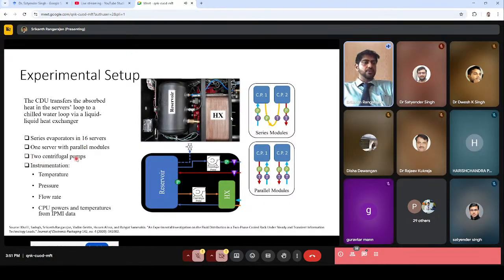And we had 2 centrifugal pumps. We did some instrumentation for noting the temperature, pressure, the flow rate, and CPU powers and temperature from IPMI data. You can see that there are two cold plates in series, which means the fluid enters here, goes through one cold plate, gets heated up, and the heated fluid passes through the second cold plate. And you also see the cold plates in parallel, where there is an individual inlet and outlet to the two cold plates, so they are not thermally talking to each other. The rack had a mix of servers, with cold plates both in series and in parallel.